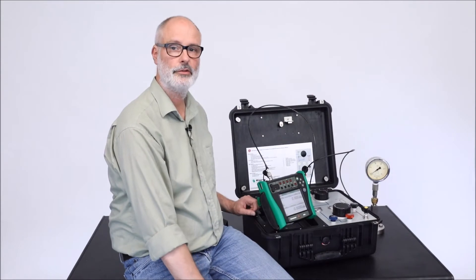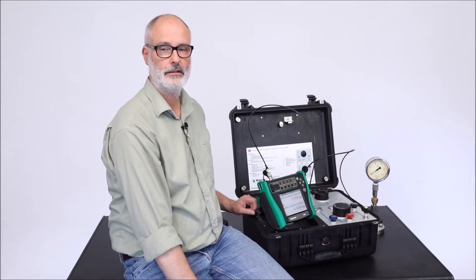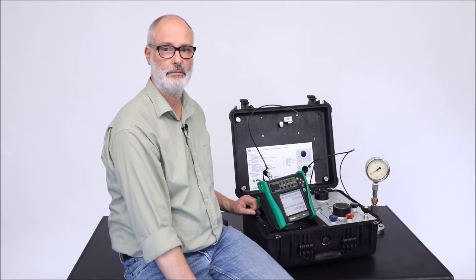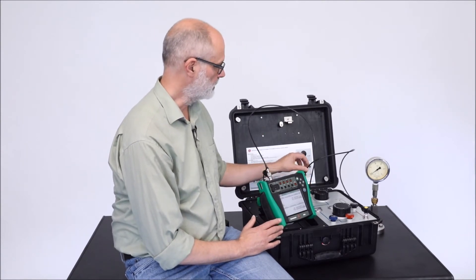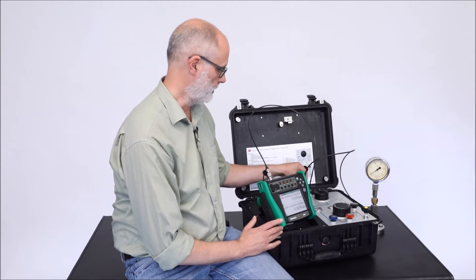Now I am going to demonstrate how to set a nominal stable pressure of 15 bar. I have connected my MC6 to one of my test ports and the device under test to the other test port.